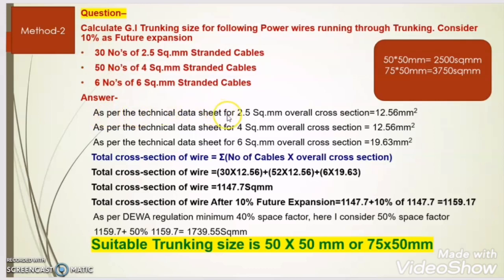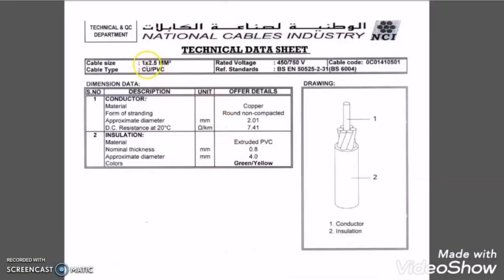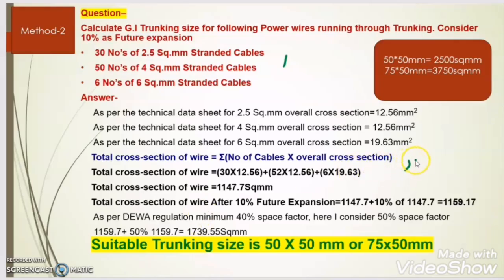As per the technical data sheet, for 2.5 sq mm the overall cross section area is 12.56 sq mm. This I took from the technical data sheet of the wire. For a 1-core 2.5 sq mm wire, the approximate overall diameter is 4mm. If we know the approximate overall diameter of the cable, we can get the cross section area using the formula π(d/2)². Applying this formula, the cross section area of the 2.5 sq mm wire is 12.56 sq mm.